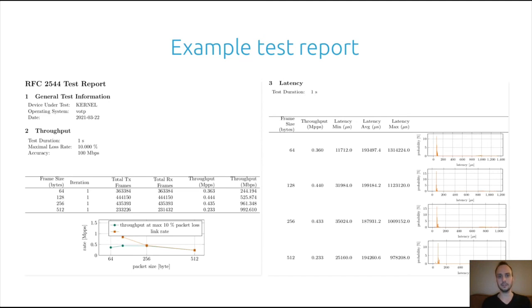Besides that, we also check interpacket latency and jitter of a sampled value stream generated by the SEAPATH platform. And we perform a round-trip latency test of a sampled value stream into SEAPATH to trigger a substation protection function on the platform, which in turn sends out a goose packet in response. This test can be repeated, injecting multiple back-to-back sampled value streams to test more resource-intensive scenarios as well.